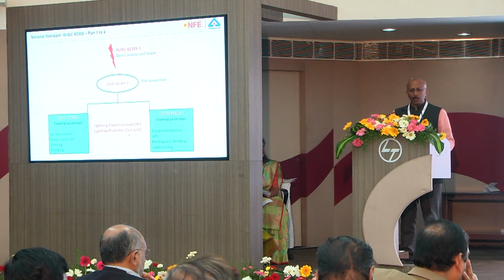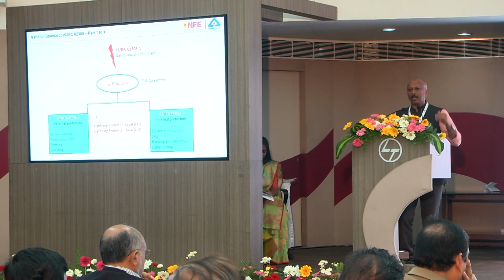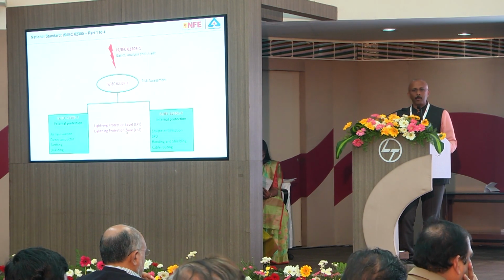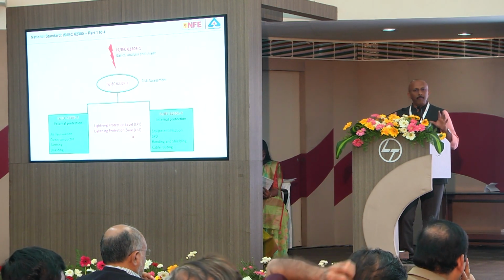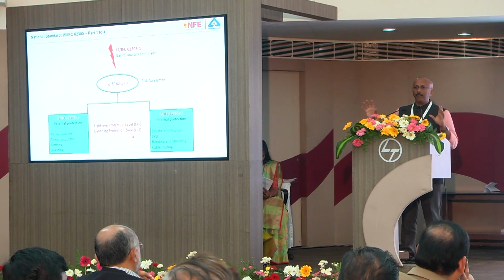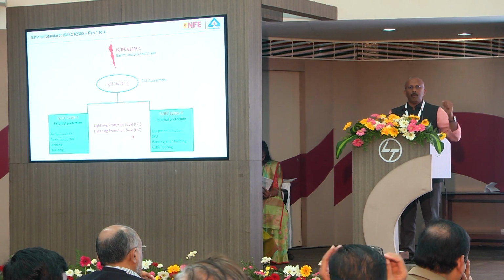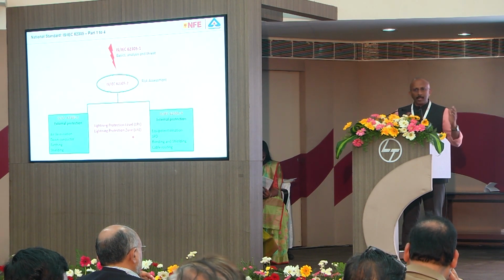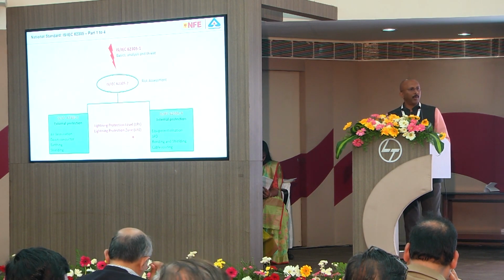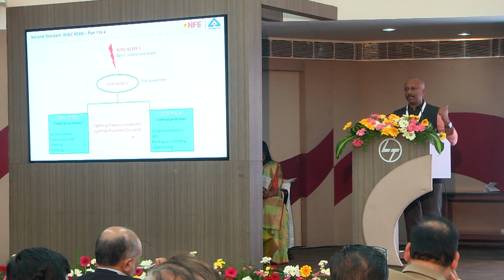Within this scope of lightning protection, in order to find out sometimes the level of protection, sometimes what kind of safety measures, or to benchmark certain requirements, the lightning protection level or lightning protection zone concepts are also introduced in the standard. But please note that the concept of lightning protection zone, LPZ, is a concept which is applicable not only for lightning protection, it is applicable for different cases. The same concept is put into the electrical installation, and sometimes this is called the voltage impulse withstanding capacity of a device, voltage impulse categorization or installation category. So all these are actually interrelated. For example, some buildings which require a very high level of protection from an EMP, electromagnetic pulse, there also the same principle is applied, but the values are different.